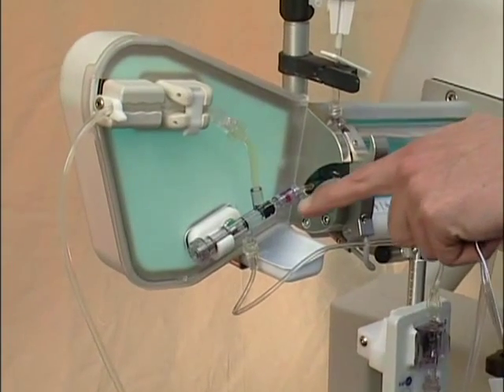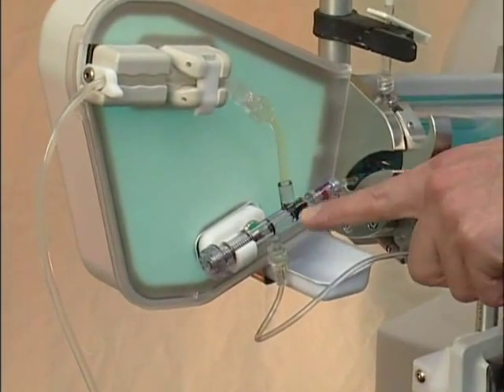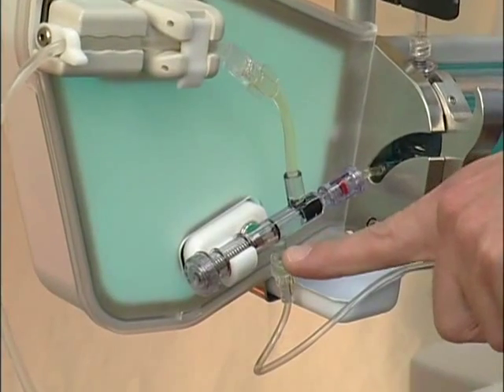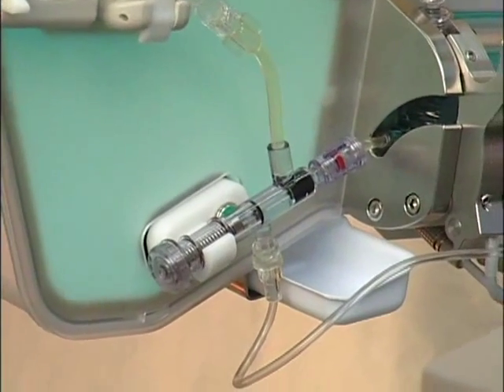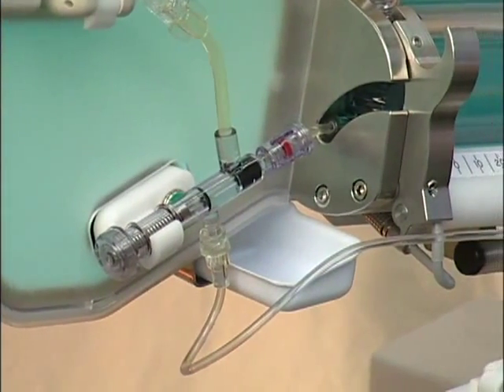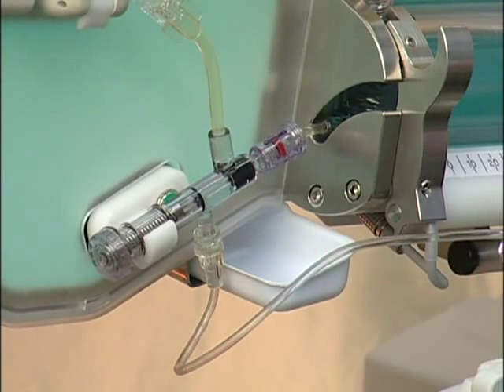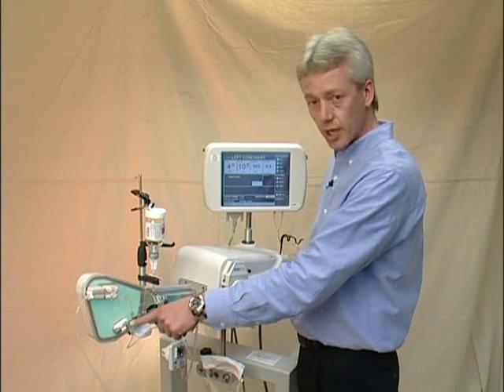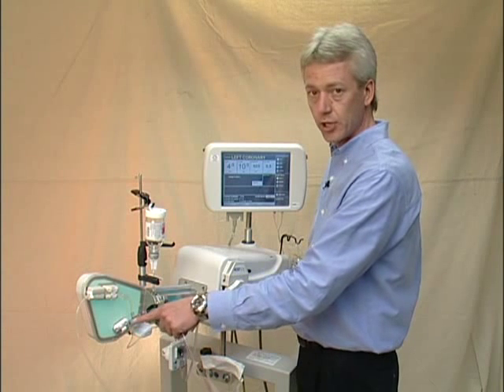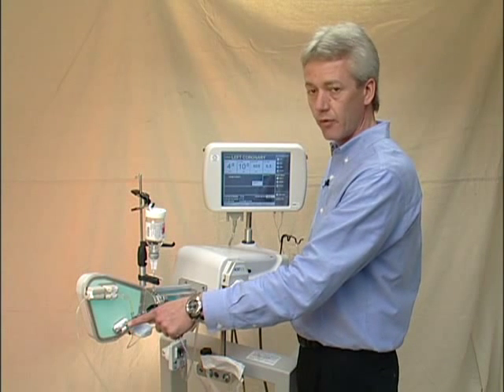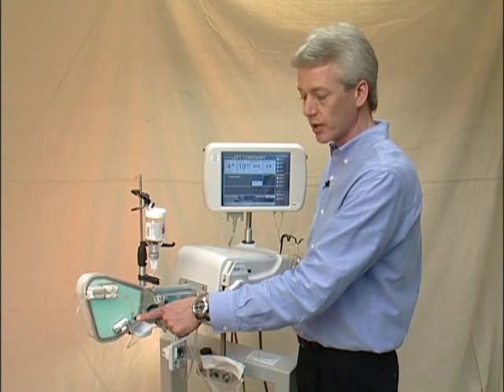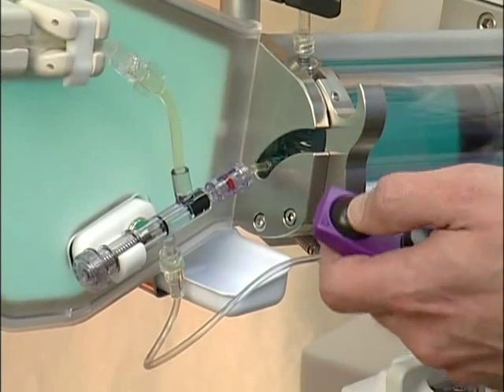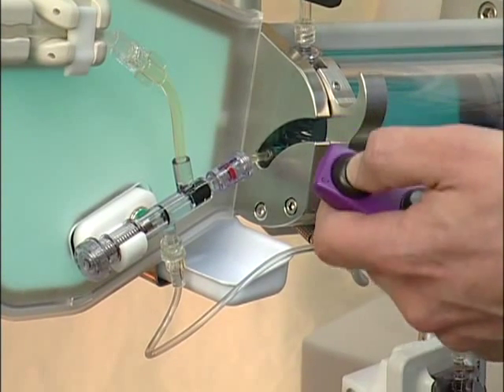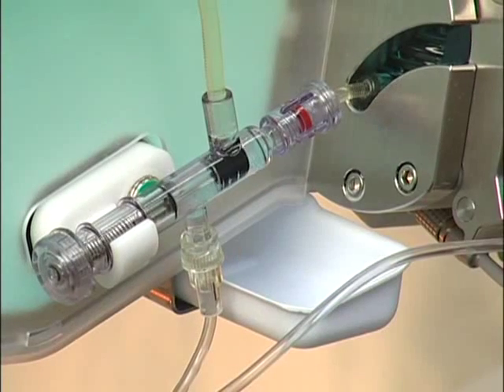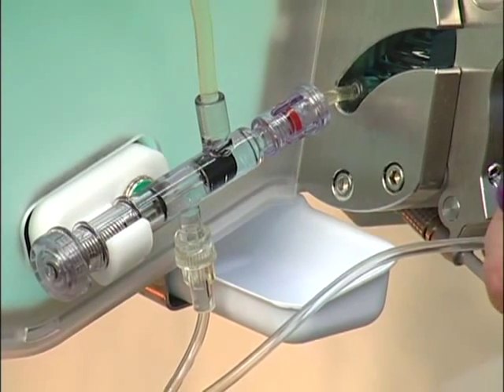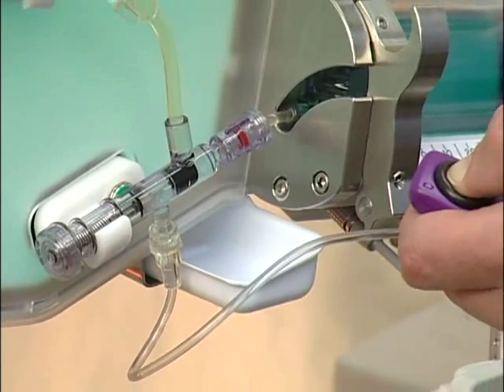The automated manifold is the unique design which allows the contrast and saline port to be switched on and off automatically. This does away with the need for the manual turning of stopcocks. This is done by closing off the saline port as we begin the injection, and the valve returns to its normal closed position once it's complete. So once you see me start pressing the button, you'll see the valve open up. After the injection is complete, the valve will close automatically.